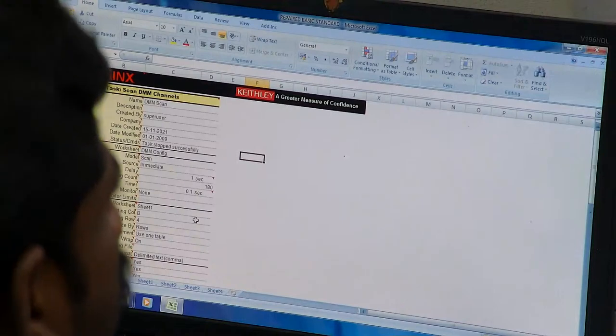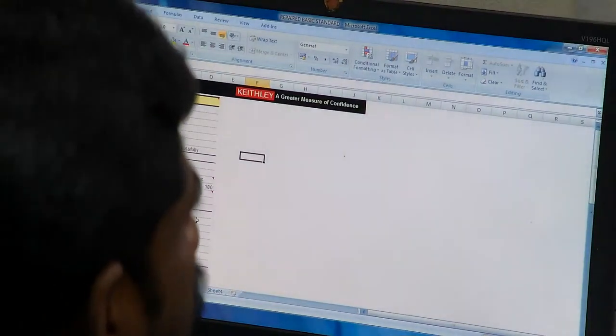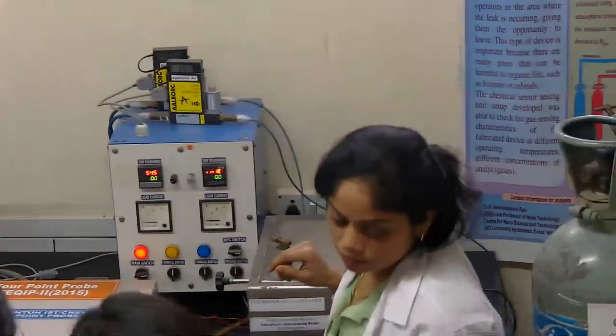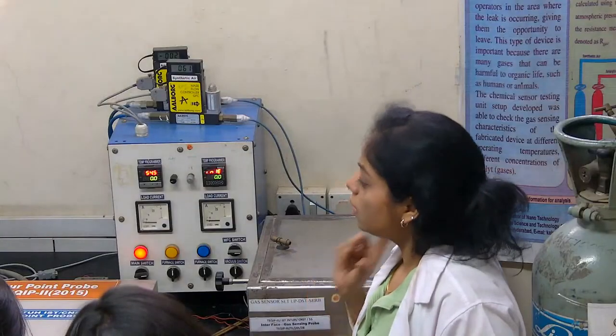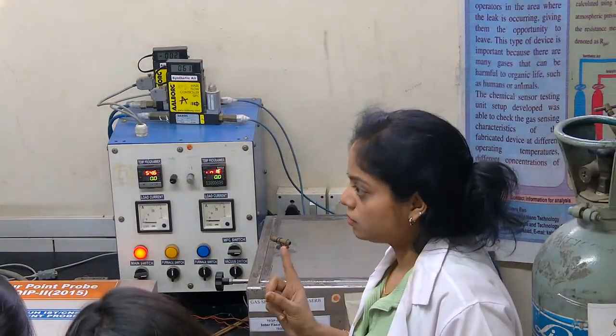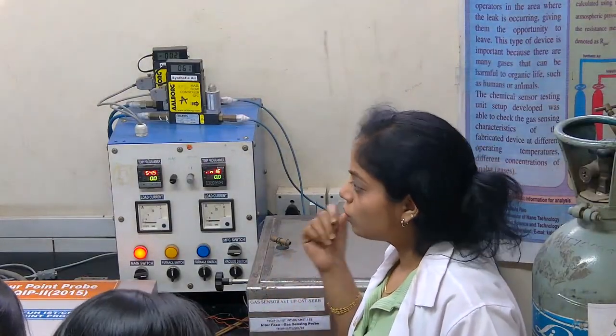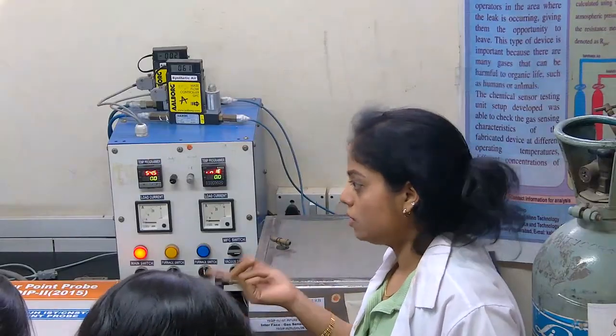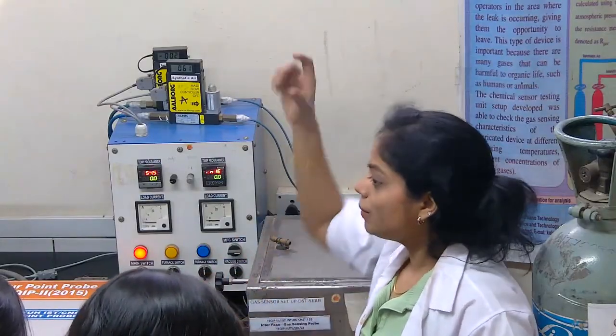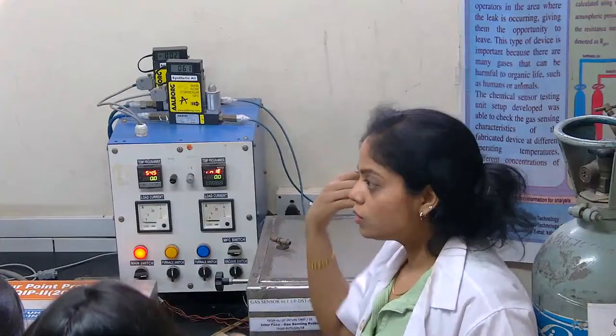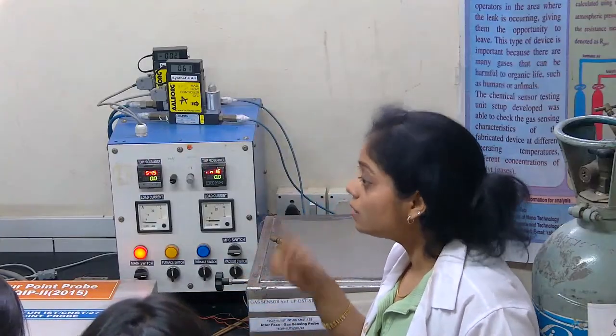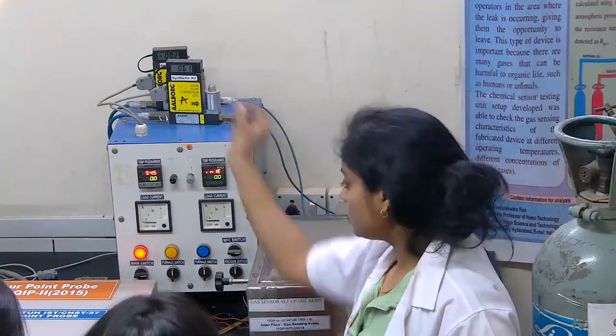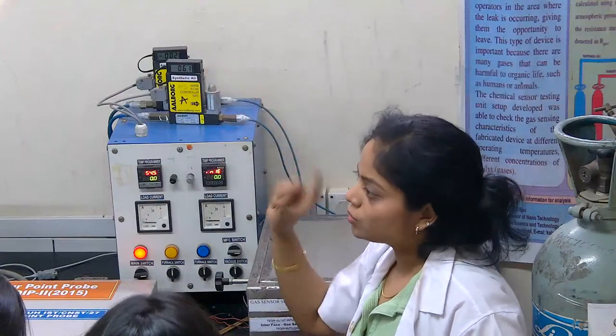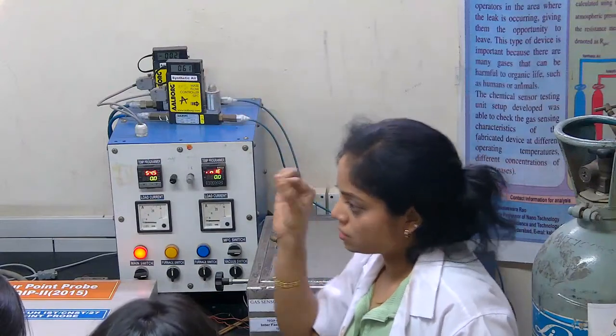So this is our synthetic air. Another important thing is, now the synthetic air is connected to this MFC, and hydrogen is connected to that MFC. Make sure that you are buying the right MFCs, because MFCs actually vary for every gas. Synthetic air will be common, but mass flow controllers differ for each and every gas. So if you're working on hydrogen, buy that respective MFC; if you're working on some other gas, make sure you're buying that MFC only. These mass flow controllers change with the density of the gases.